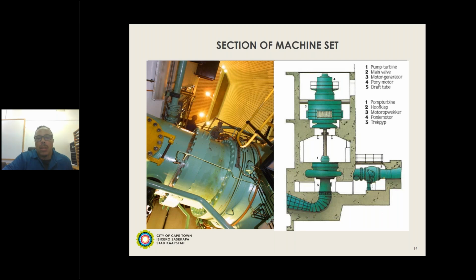At the end of the run, when we're shutting down from generate mode, the unit is obviously running at 600 RPM. We then shut down, we close off the MIV at 2, and then the system runs down under gravity on fairly important bearings, pressurized with oil. It runs down to about 340 RPM. And then what happens is that the pony motor acts as a dynamic brake, and it basically counteracts or opposes the inertia or force applied by the turning shaft. So it's just to get the machine to run down a lot quicker.